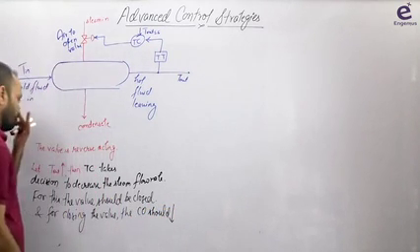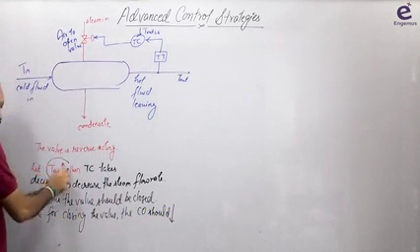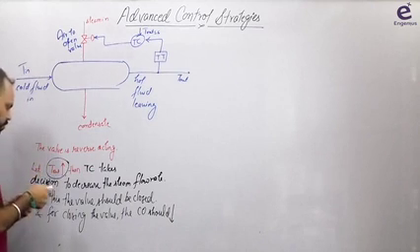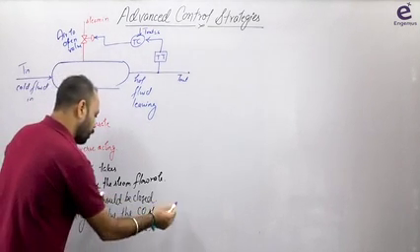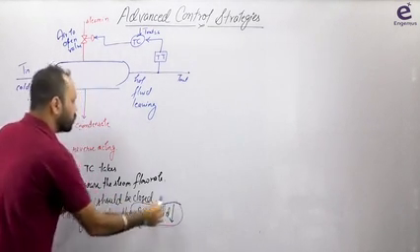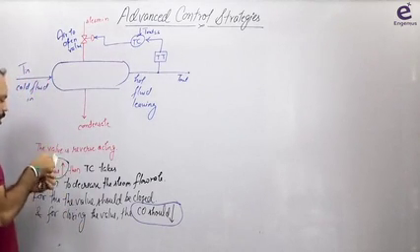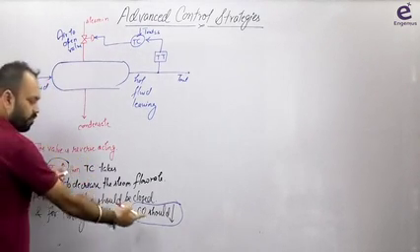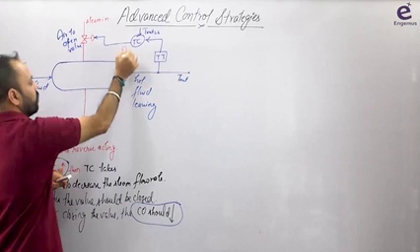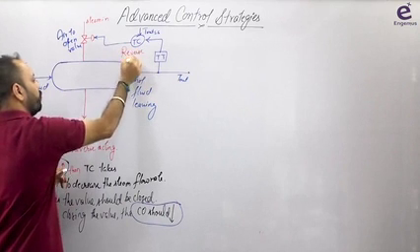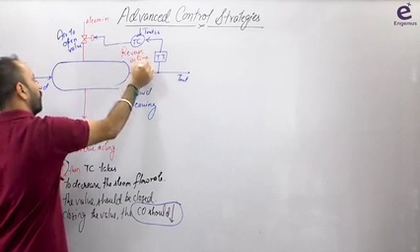How to check? You saw that T out increases, measured variable increases, and controller output decreases. Means what type of nature, what is the nature of the controller here? Controller is reverse acting, because this nature are opposite. Controller is reverse acting.